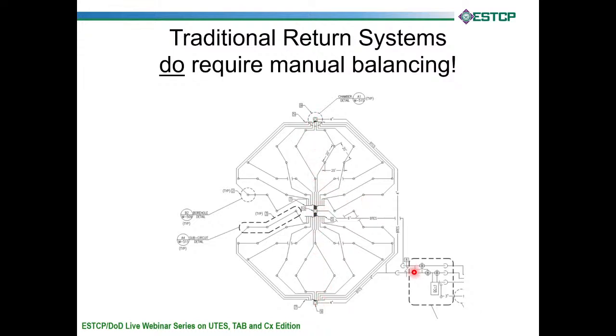So our water is coming in. Remember, it can flow either way, but just for discussion purposes, we're going to pretend it's flowing this way in the direction of my pointer. Hits the core vault first, is distributed to all these circuits. Each one of these circuits goes through the three boreholes in series, hits the perimeter vault where our balancing valves are, comes back on the return, and heads back out to the building.